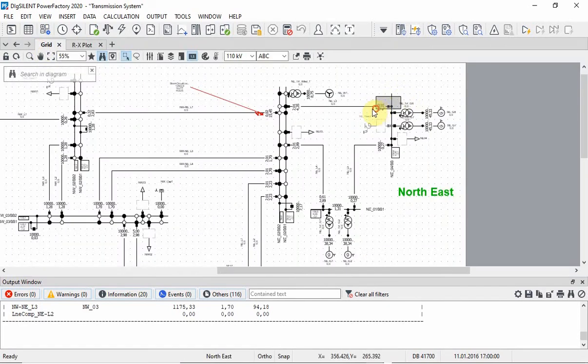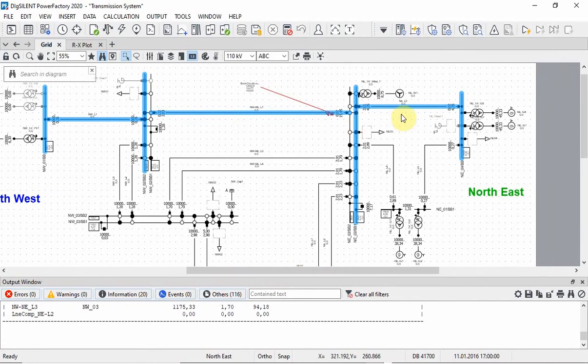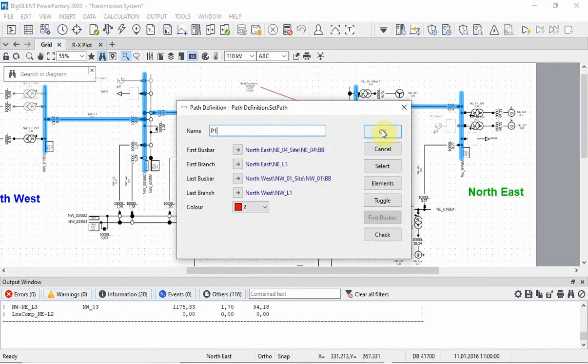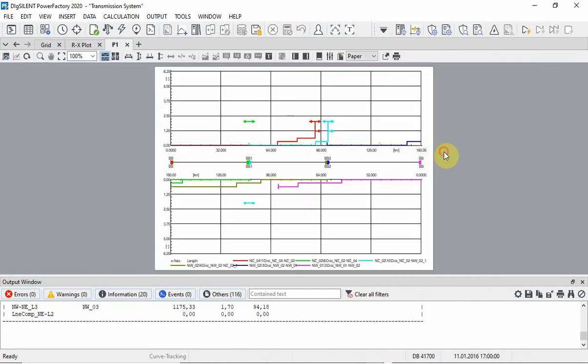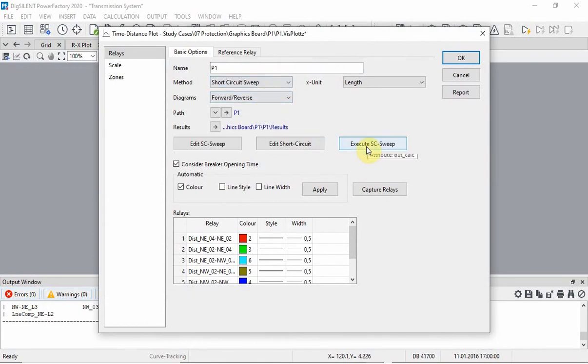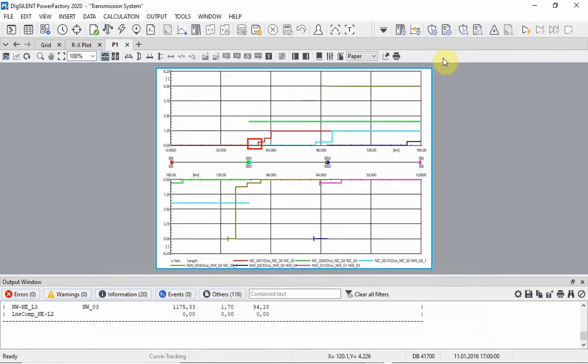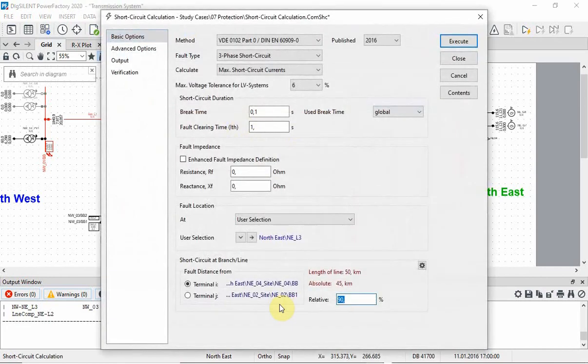Let us have a look at a time-distance plot. For the time-distance plot we will need to define a path that contains the relay of interest. The relay of interest is the red one. Now let us run a three-phase short circuit sweep. You can see that the first zone is too long and that there is interference with the light blue relay in the neighbouring station. This has to be changed — we will limit the first zone to 80% of the line length.